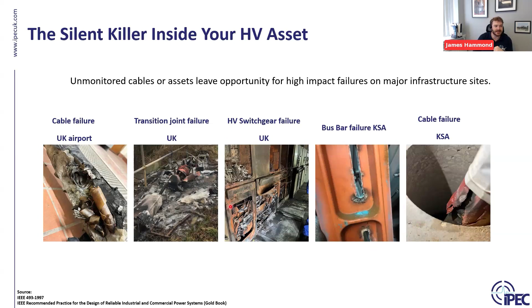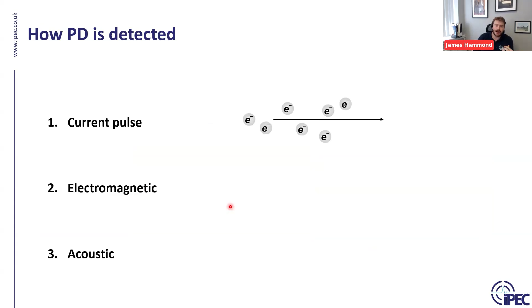It can be detected. This is how it's detected. This little electrical spark is generating energy, so it can be a form of current pulse. A couple of examples of how that can be detected: a HFCT, TEV. I'll go into these a little bit more in a second. It can be an electromagnetic pulse. Again, electrical energy, you've got that electromagnetic pulse generation. These can be detected in the ultraviolet range, in the ultra high frequency range, things like that. And then acoustically as well. Often this is in the kilohertz range, like 40 kilohertz is where it's most common or most easily detected.